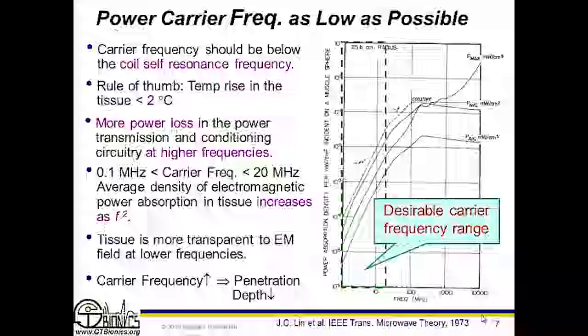Forget about gigahertz. You should try to avoid that and go to lower frequencies, because, as you can see in this steep curve, the lower the frequency, the more transparent the tissue and the water is to the electromagnetic field. So lower frequency, more penetration into the body. Higher frequency, more absorption in the body, and what does that energy turn into? Heat. Very dangerous. We try to avoid that. But here is where the challenge comes. For power transfer, you use low frequency, but when it comes to delivering data through an electromagnetic field, there is a direct relationship between the bandwidth, basically how much capacity this electromagnetic link has for delivering data, and the carrier frequency. So you see that you have a huge dilemma on your hand. For high power transfer, lower frequency is better for obvious reasons.